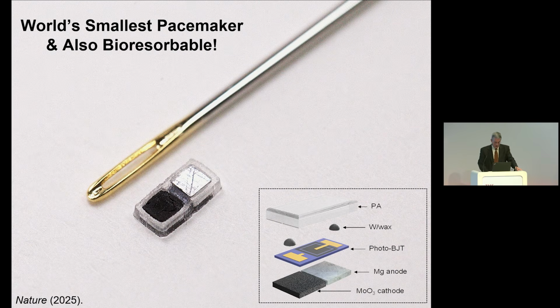How do I operate it then? The other side of the device consists of a photoactivated switch. I won't get into the details of this, but when you illuminate this device with near-infrared light, that switch closes and the battery can then discharge current into the cardiac tissue. If I'm not illuminating the device, that switch is open and the battery cannot discharge current into the cardiac tissue. And near-infrared light has a very deep penetration depth into soft living tissue.